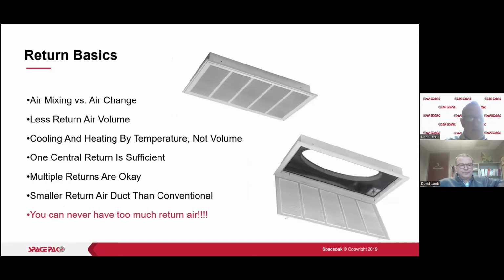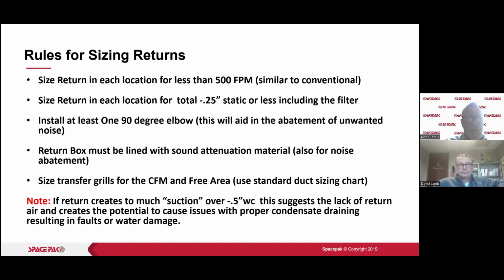All right, air mixing versus air change. We talked about that, less air volume, and central return. So I'm going to skip through that. All right, size return in each location for less than 500 feet per minute. You're not going to find filters that are rated above 550 feet per minute anyway. Size return in each location for a total of negative 0.25, 1/4 inch of static or less, including the filter. Install at least one 90-degree elbow on the return.